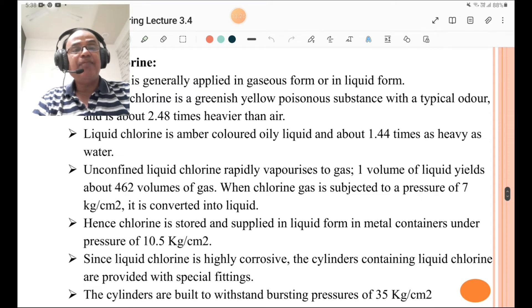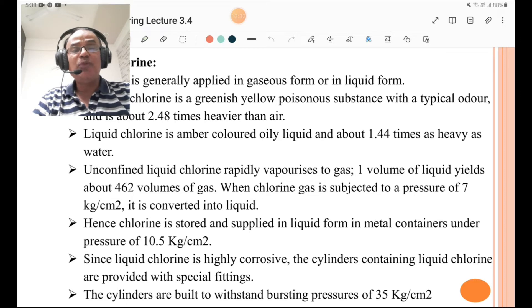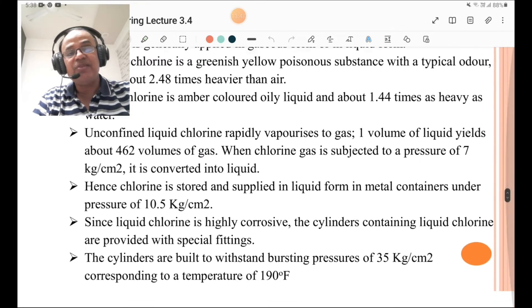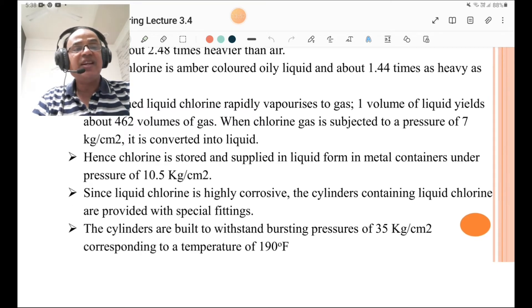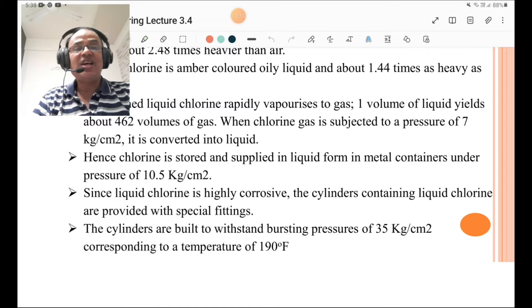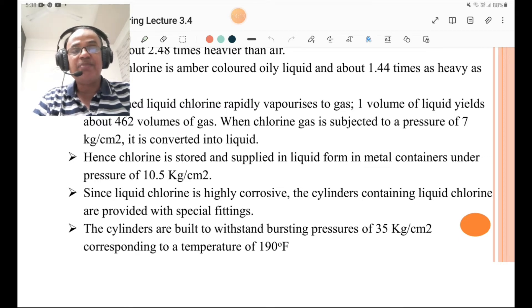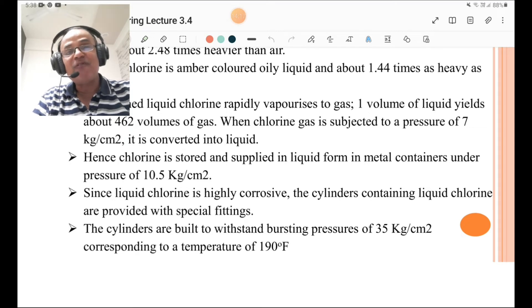Unconfined liquid chlorine rapidly vaporizes to gas; one volume of liquid yields about 462 volumes of gas. When chlorine gas is subjected to a pressure of 7 kg/cm², it is converted into liquid. Hence chlorine is stored and supplied in liquid form in metal containers under a pressure of 10.5 kg/cm². Since liquid chlorine is highly corrosive, the cylinders are provided with special fittings. They are built to withstand a bursting pressure of 35 kg/cm² corresponding to a temperature of 190°F — these values are often asked in multiple choice questions.